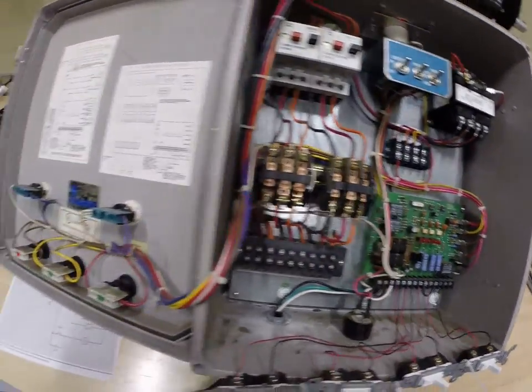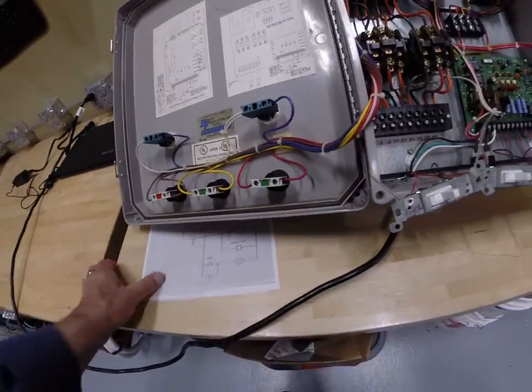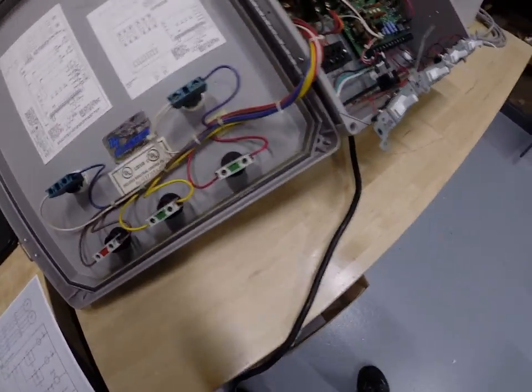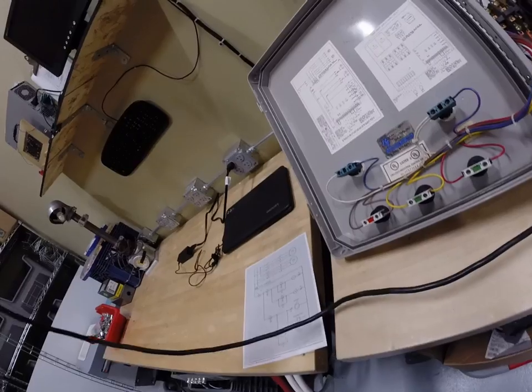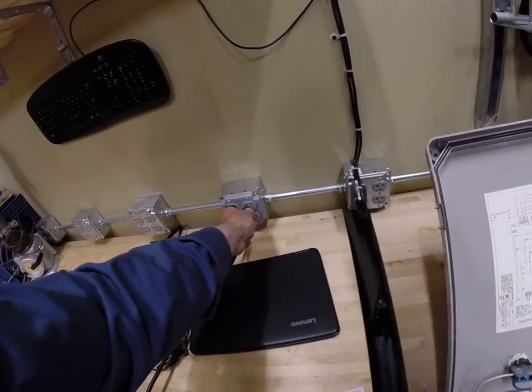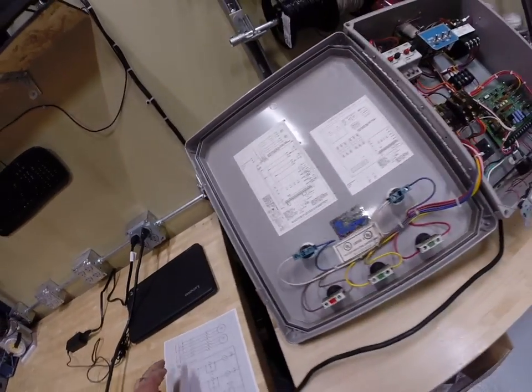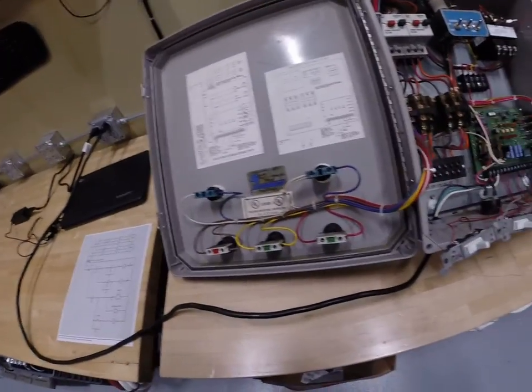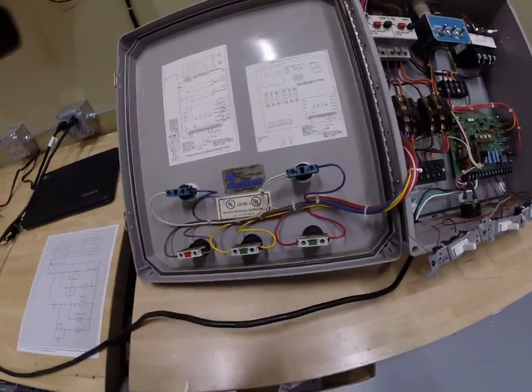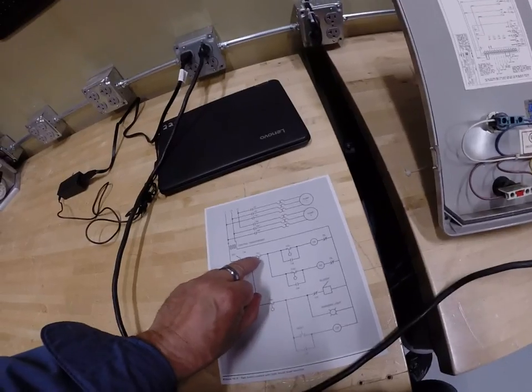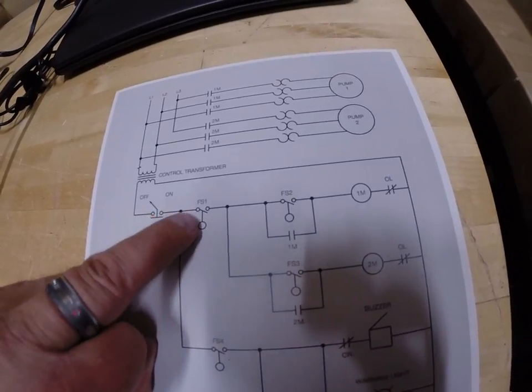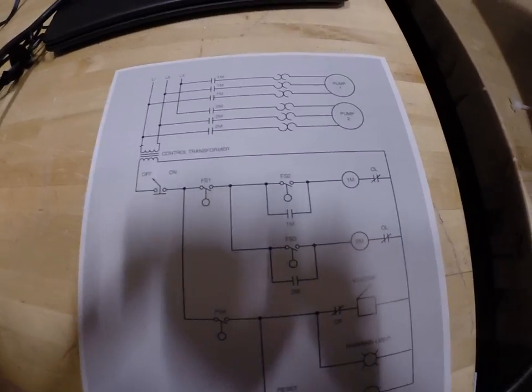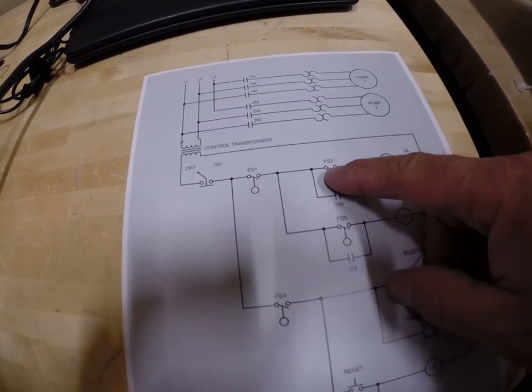So if I had to simulate this, what I did was I hooked up a 120-volt power cord to the bottom of this enclosure so I can simulate this. I'm just going to plug it in so it's in kind of status mode. I may have to put my camera down for a couple instances. But if I walk you through this circuit, I'm going to turn on float switch number one. When we turn on float switch number one, all that does is it brings power to float switch number two.